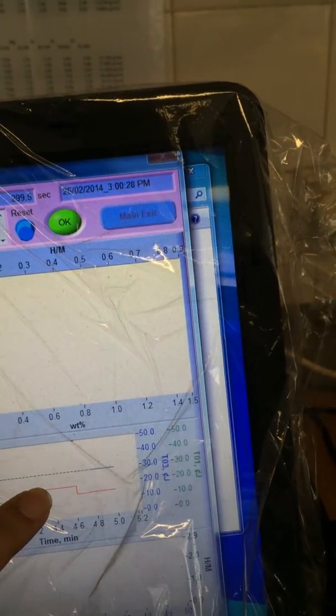So this is basically charging right now for 1 minute. You look at the pressure curve, it's charging. This one is not counting anything, no timing. When it reaches 2.5, it stops. Then it opens the valve, and when it reaches stability, it drops. And this starts counting for another 1 minute. So now is the first cycle.